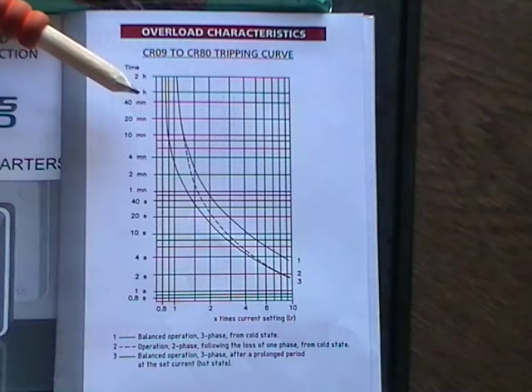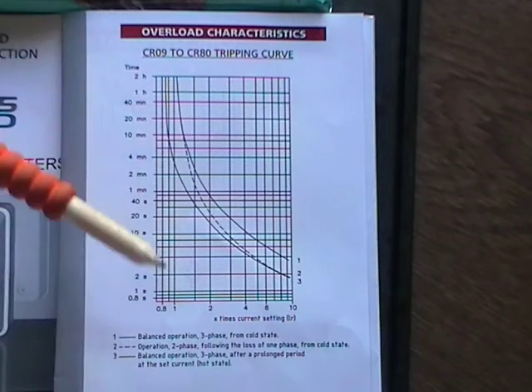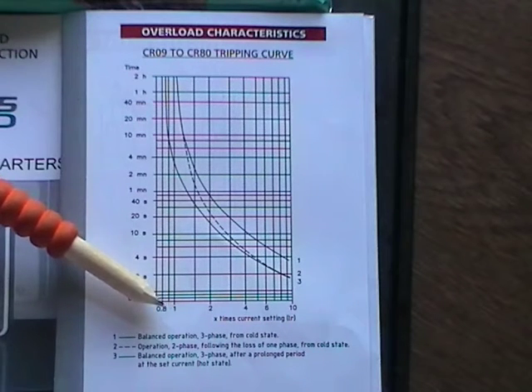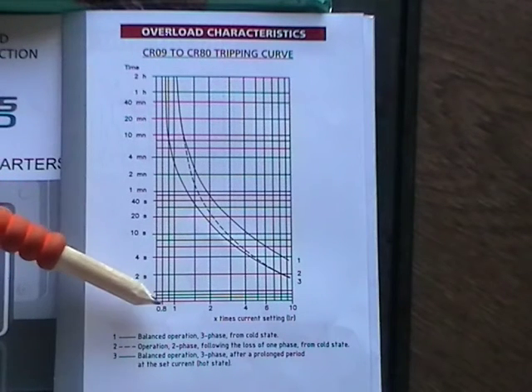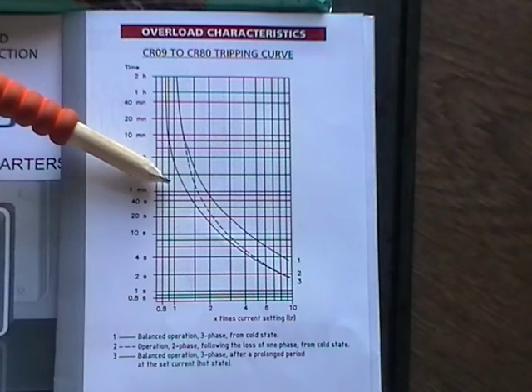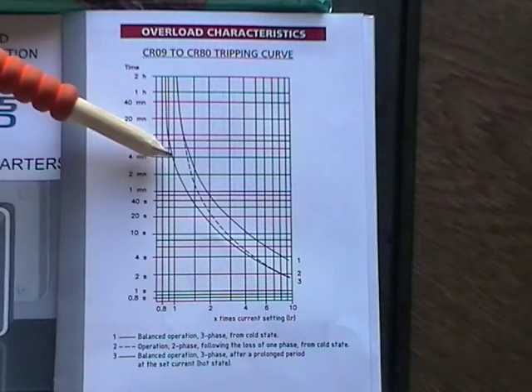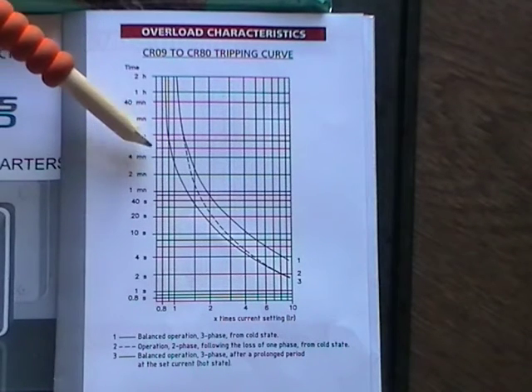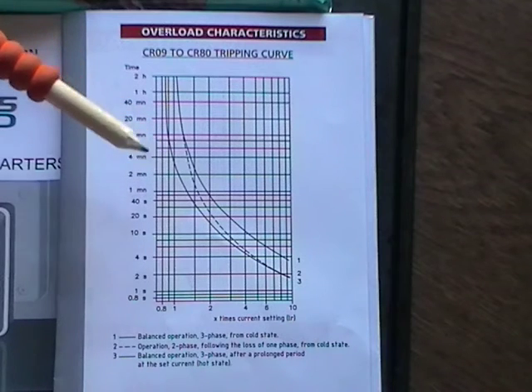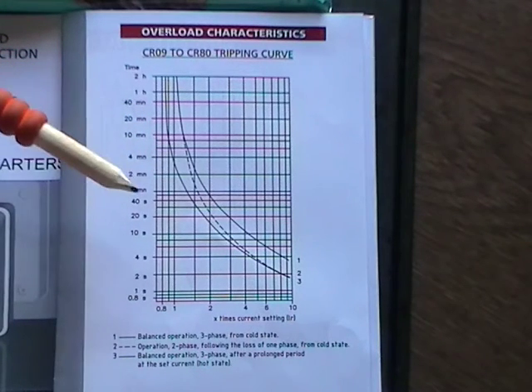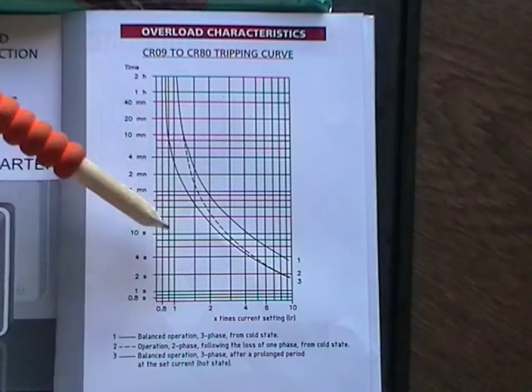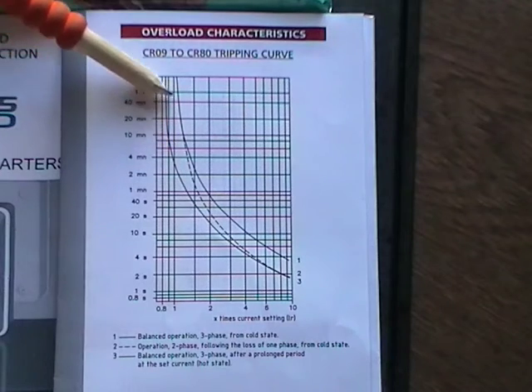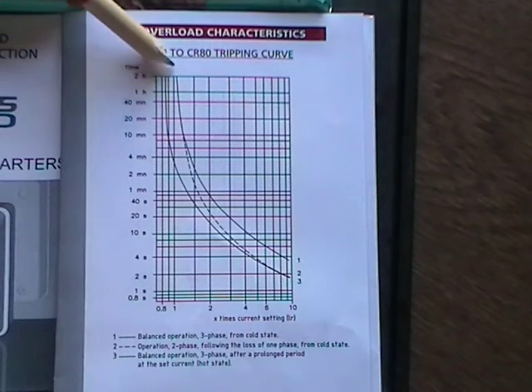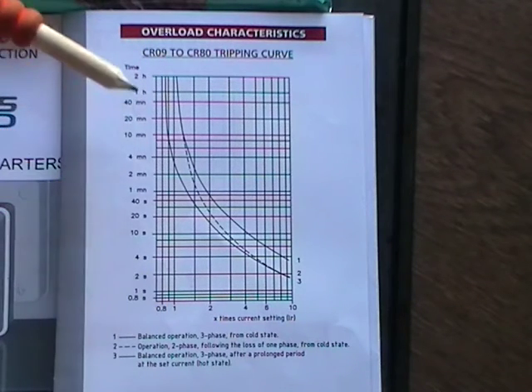So if we say we set the trip to 10 amps, then this 1 represents 10 amps as being the full load of the motor. And from that, if we follow that up the timeline, we can see that on a warm motor at 10 amps it would trip at just before 4 minutes. However, most motors are started and stopped, and so we can assume that we're running from a cold motor, and at 10 amps the cold motor curve goes over 2 hours, possibly up to about 4 hours. So at full load this would allow the motor to run for about 4 hours before it tripped.